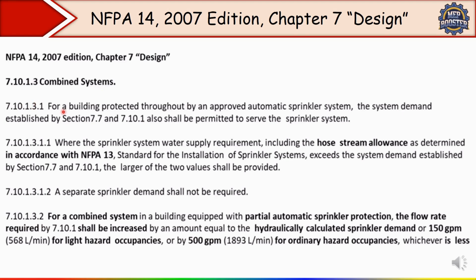The first point: for a building protected throughout by an approved automatic sprinkler system, the system demand established by section 7.7 and 7.10.1 also shall be permitted to serve the sprinkler system. Okay, so it means what? Suppose a building is fully protected with an approved automatic sprinkler system, then the water supply must be designed to meet the greater of the following. Means the greater of the system demand for sprinkler as per NFPA 13, okay, and the hose stream allowance for the standpipe system. That is written here.